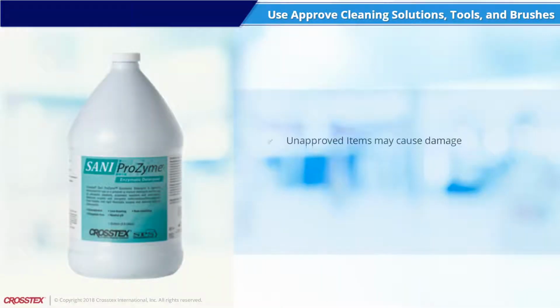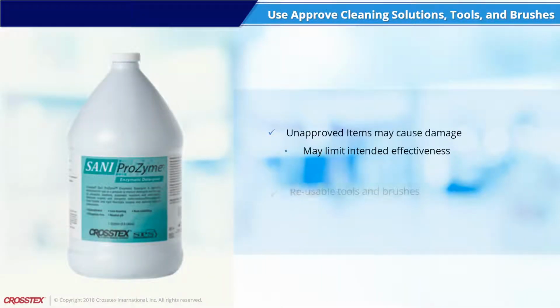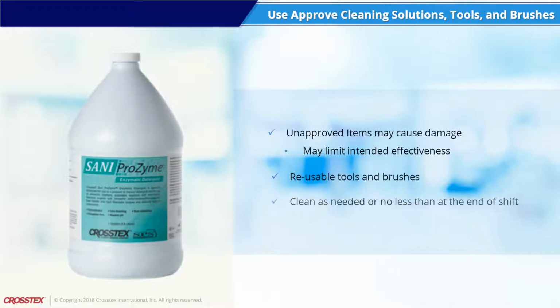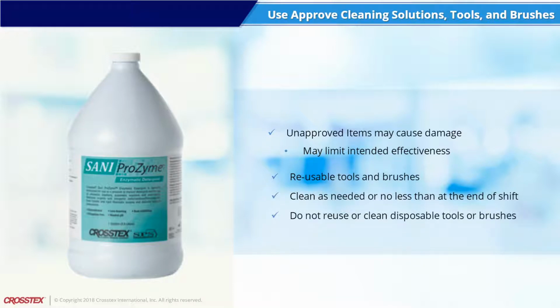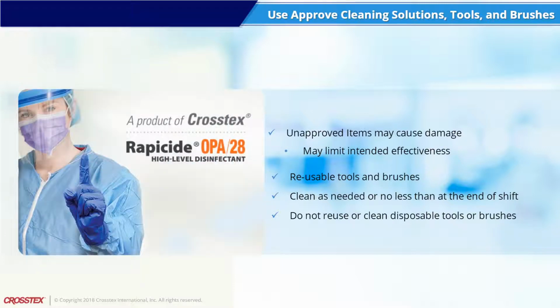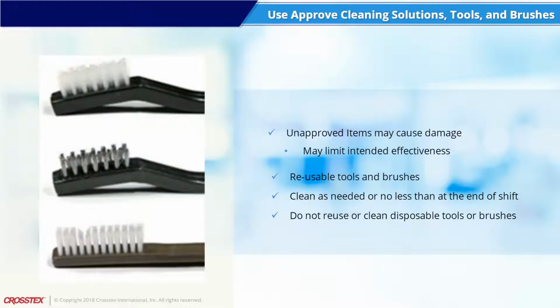When cleaning reusable equipment, be sure to use approved cleaning solutions, tools, and cleaning brushes. Unapproved cleaning solutions and commercial products not intended for use on medical instruments can cause damage or limit the intended effectiveness. Reusable brushes and other tools should be cleaned, disinfected as needed, and no less than at the end of each shift. Disposable brushes should not be reused, even if disinfected, and should be discarded after each use.